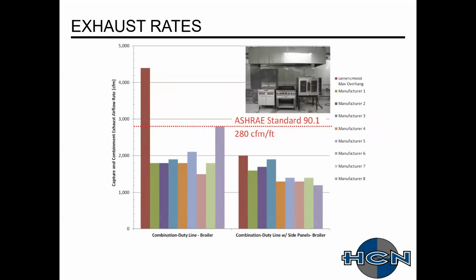The benefits there. This is a mixed flow, mixed equipment kind of configuration. Typically, that's what you're going to see in most commercial kitchens. You're not going to just have all ovens unless they're doing some prep stuff. A 10-foot hood with fryer, broiler, you can do a range, griddle, and then an oven. It's a pretty standard concept for most restaurants. They did 8 different manufacturers and then a generic sheet metal hood. They tested the CFMs, used the Schlieren cameras, and basically ASHRAE 90.1, that's the standard. What they're looking for is, for heavy duty, 280 right across. So all your listed manufacturers are pretty much under that.